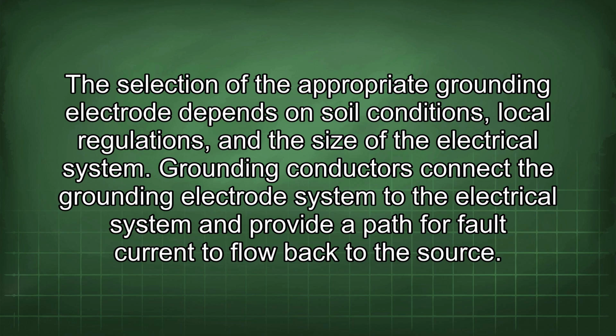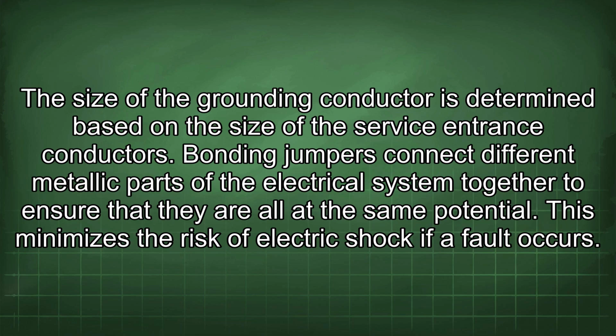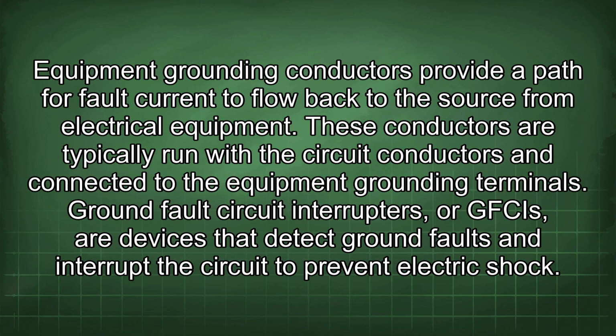Grounding conductors connect the grounding electrode system to the electrical system and provide a path for fault current to flow back to the source. The size of the grounding conductor is determined based on the size of the service entrance conductors. Bonding jumpers connect different metallic parts of the electrical system together to ensure that they are all at the same potential. This minimizes the risk of electric shock if a fault occurs. Equipment grounding conductors provide a path for fault current to flow back to the source from electrical equipment. These conductors are typically run with the circuit conductors and connected to the equipment grounding terminals.